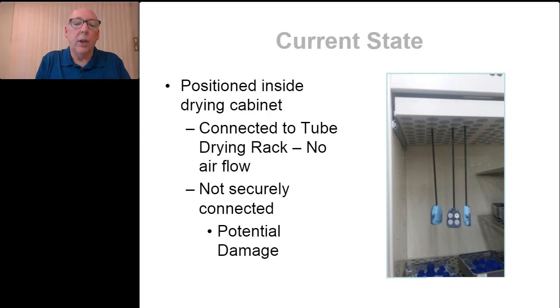Here's something else that I've seen with some hospitals, is positioning the devices inside a drying cabinet, which is terrific to do because certainly they'll dry through convection. But if you take a look at the ceiling of this picture of the drying cabinet, that's a tube drying rack. That's really intended for larger bore, larger lumen devices, such as those that come from respiratory or anesthesia. And the air that can flow through there, in this picture, the ports are on the other end. So air is not flowing through any of those shafts at all that you see there. And again, another potential for damage if those devices slip out of there. So those tube drying racks are really intended for larger bore tubing that may come from respiratory, anesthesia, etc.